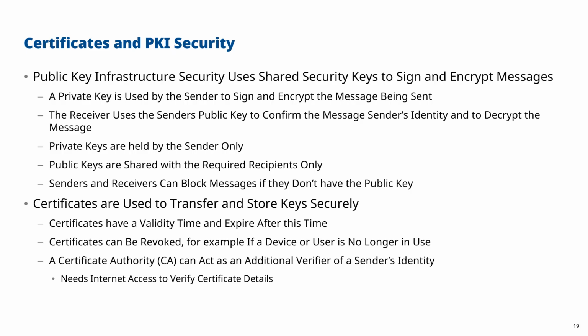Certificates are used to transfer and store keys securely, and certificates themselves have a validity time and they expire after this. This is actually a challenge for OT applications because a typical certificate validity is 5 years, and at the end of that you would have to issue and manage a new set of certificates. But to simplify that, some devices, including Emerson, can be configured to ignore that validity time, because there is a risk that suddenly after 5 years all your communications will halt and your plant will shut down.